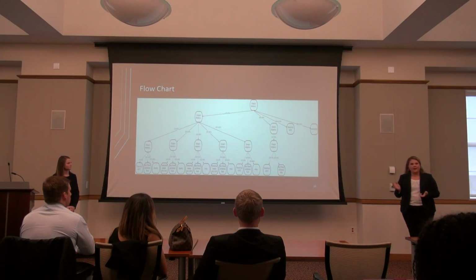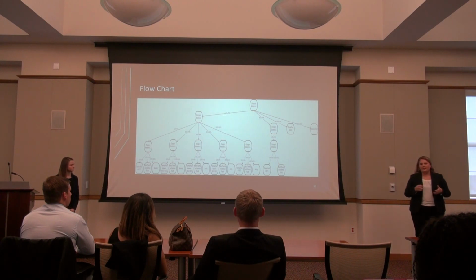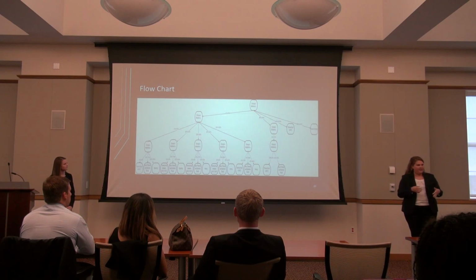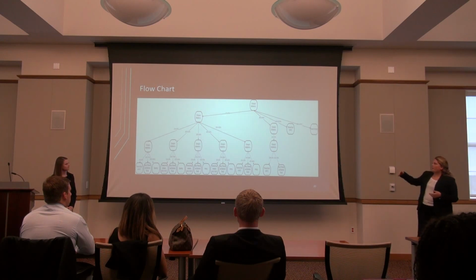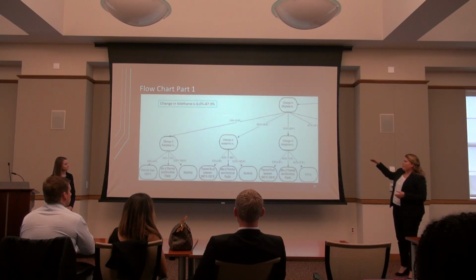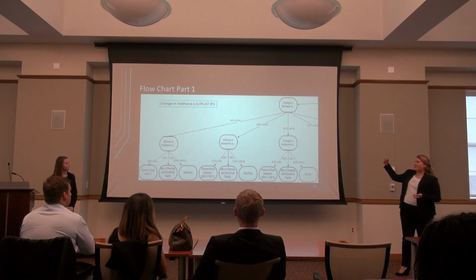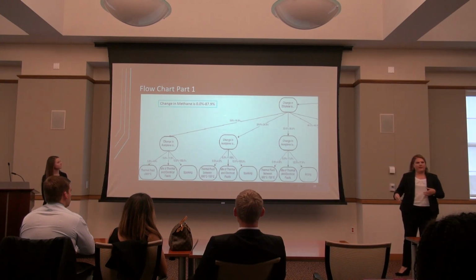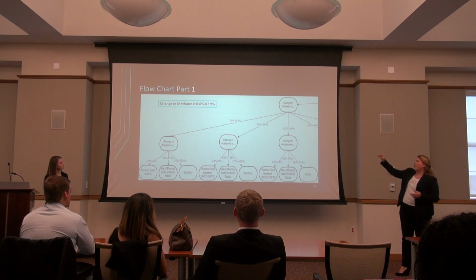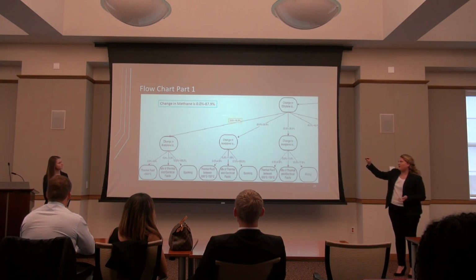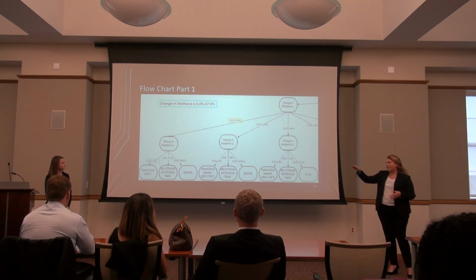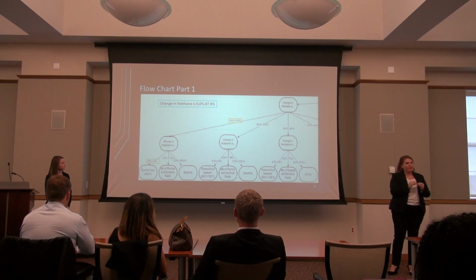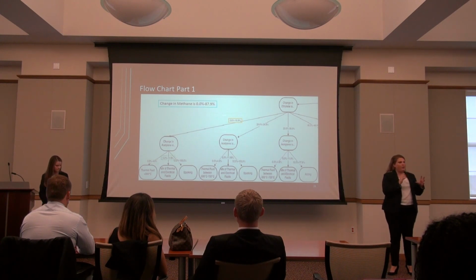So the first thing we created was a flowchart, mostly based on the Duval triangle - it's like an if-then analysis. First it goes through the levels of methane, and for example on this side, if it's in the range between 0 and 87% increase, then we move on to ethylene, to the first range, 0 to 19.9, then to acetylene, and it determines based on that particular reading what problem we have.